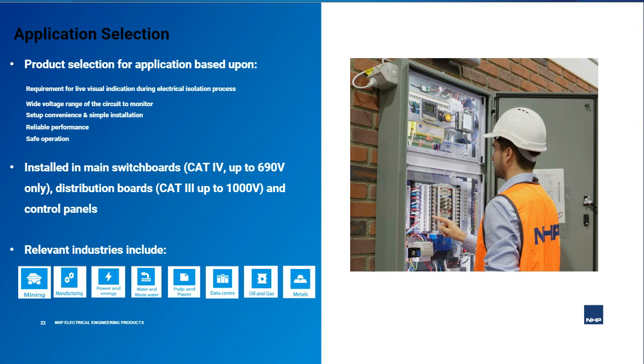Other points which will be considered when selecting a liveline indicator: the voltage range that the unit can monitor. Remember, both the lower and the upper limits of the voltage are important to consider in terms of selection. Simplicity in terms of the setup and installation, and not only in the new panels, also for retrofitting. Overall reliable performance. It's important that the unit functions correctly and does what it's spec'd for, and that too over a long time period.